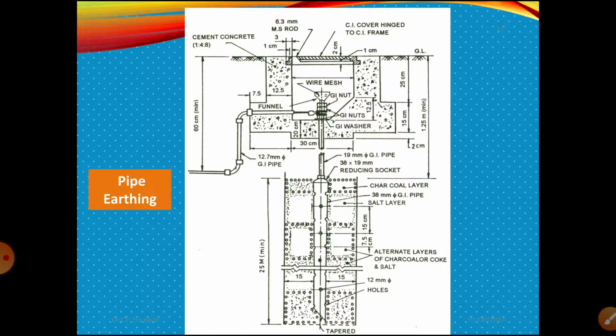Another pipe of 19 mm diameter and 1.25 meters length is connected to the 38 mm pipe through a 38 into 19 reducing socket. At the top, a cement concrete work is made and provided with a funnel with wire mesh to pour water frequently to maintain moisture in the system and reduce the earth resistance. The funnel is connected to the 19 mm dia pipe by means of bolts and nuts. Another pipe of 12.5 mm dia is connected to the 19 mm pipe near the wire mesh. The earth wire is carried to a depth of 60 centimeters through a 12.5 mm pipe.